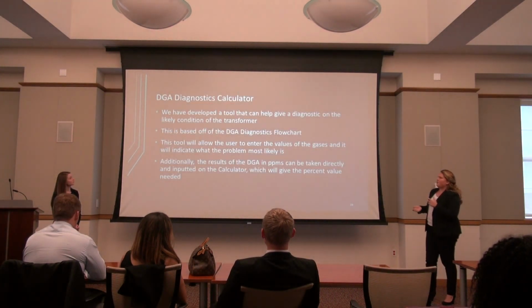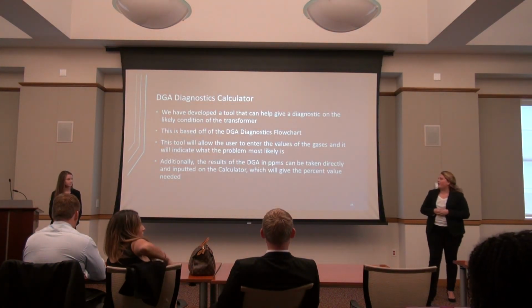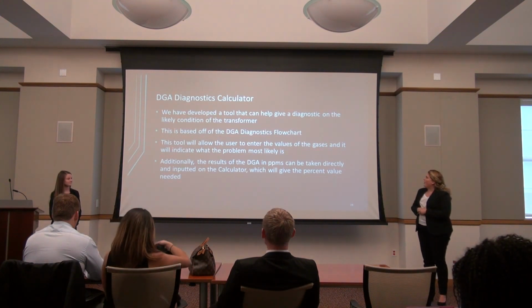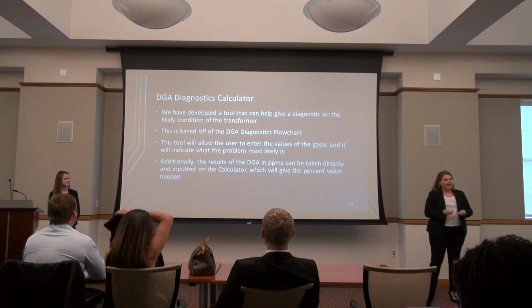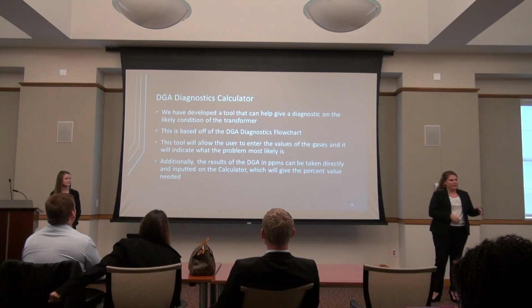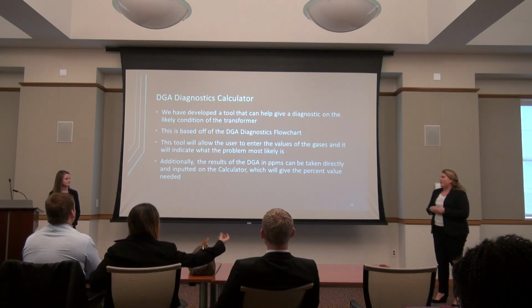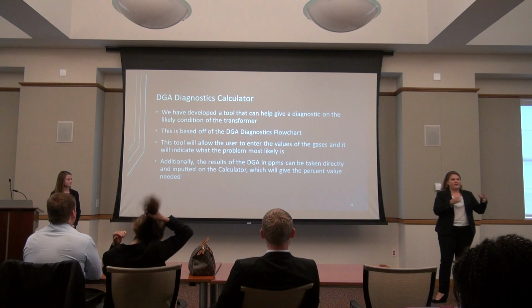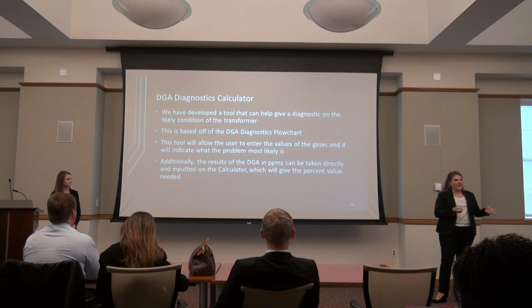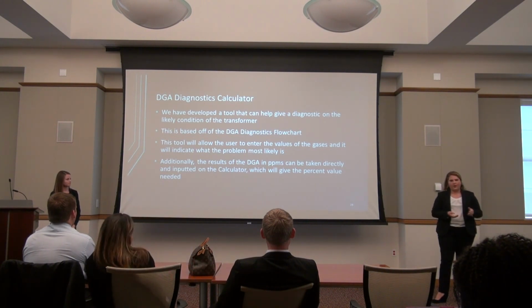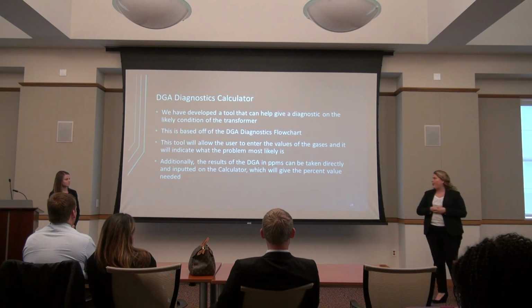This DGA diagnostics calculator, that's how we're calling it, we developed so it can give you the one likely condition that's occurring within the transformer. It's based off of the flow chart, which is based off of the Duval triangle. So all of these data points and everything, they're used in practice. We're not just coming up with them from nowhere.